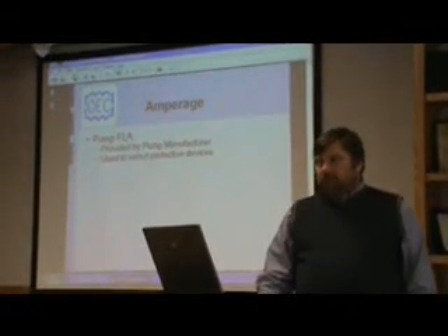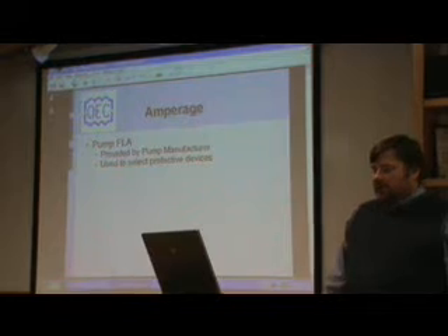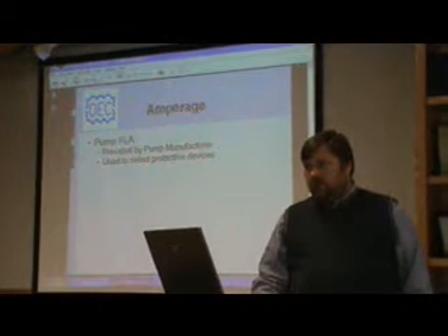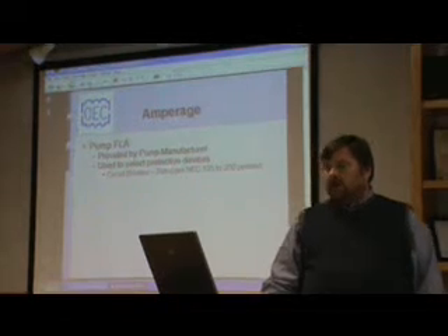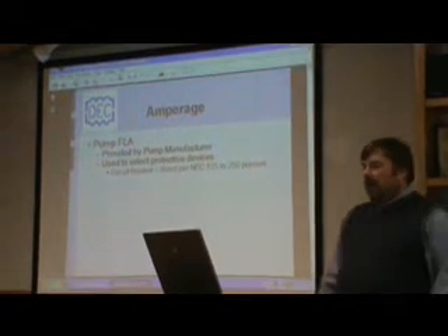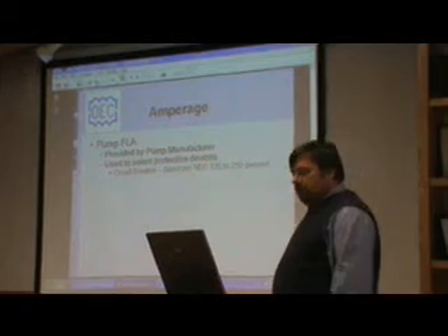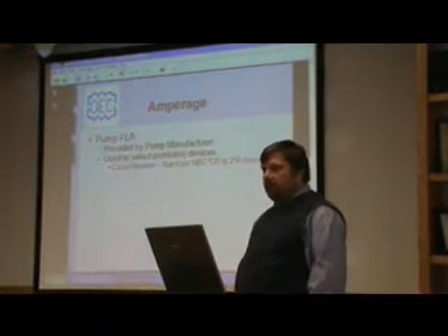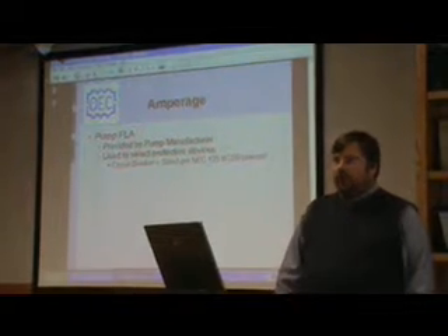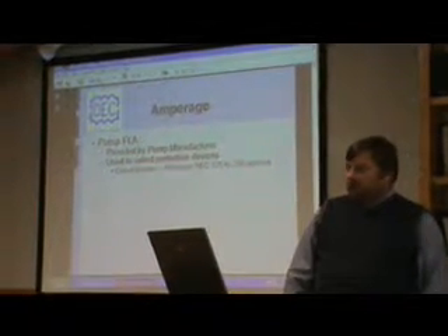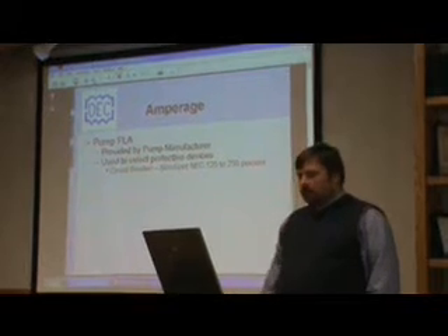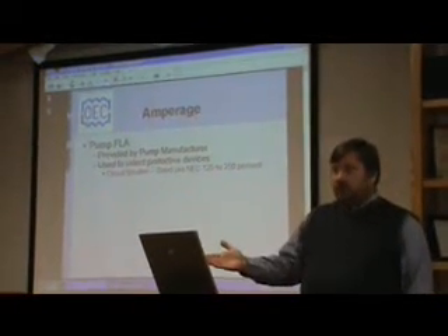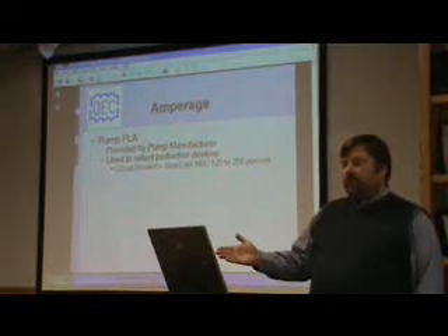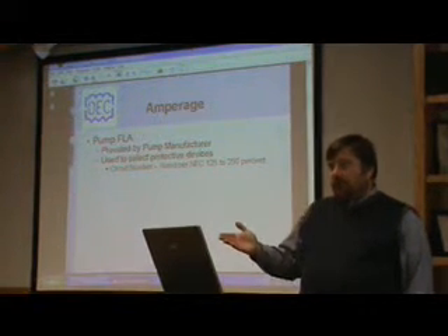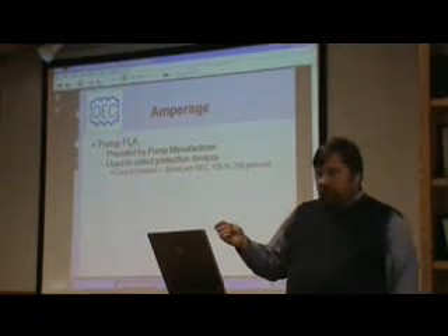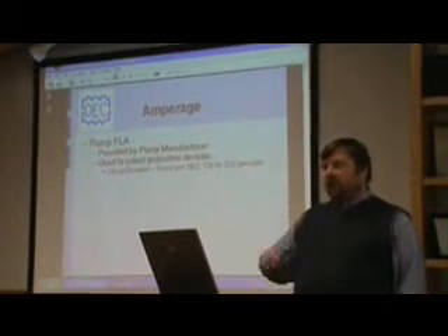The first thing we use it to do is to select your protective devices. When we talk about the protective devices, we're talking about circuit breakers, overloads, and things like that used to protect your motors. A circuit breaker in the panel, per National Electric Code, is sized 125 to 250% of that full load amps. So at Ohio Electric Control, when we size the starters for a case where we're looking at a pump, if your pump is pulling 10 full load amps, the circuit breaker would be sized at 13 amps. There's not a 13 amp circuit breaker in most cases, so we take that up one step to the next available size, which would be a 15.